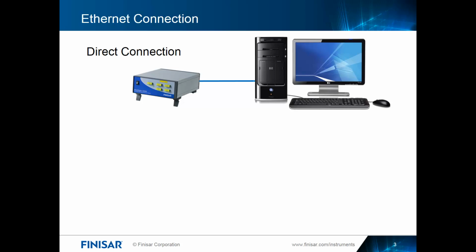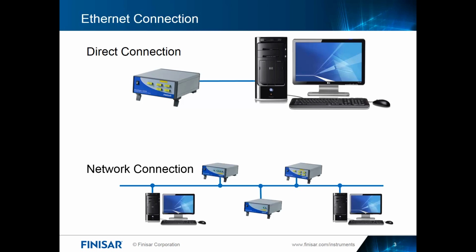There are two ways to connect to the WaveShaper using the Ethernet port. A direct connection, as shown here, where the WaveShaper is plugged straight into an Ethernet port on your computer, or a network connection, where both the WaveShaper and the computer are connected to the same network. When connected to a network, you can control multiple WaveShapers in a single session, or alternatively, multiple computers can connect to and control a single WaveShaper.